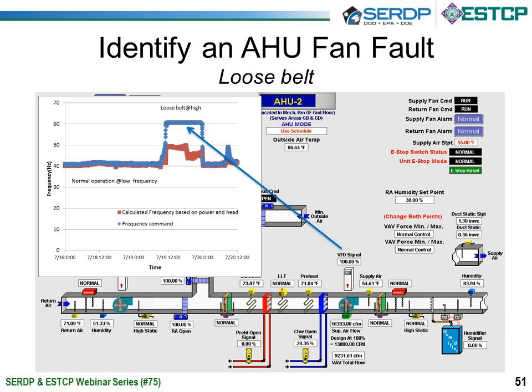What we can do to detect a loose belt is to monitor the frequency from the VFD, which is a representation or a surrogate for the fan flow rate. Blue represents the frequency command, that is the speed being requested of the fan. And the red represents the virtual calculated frequency based on the power and head that are measured from the VFD.